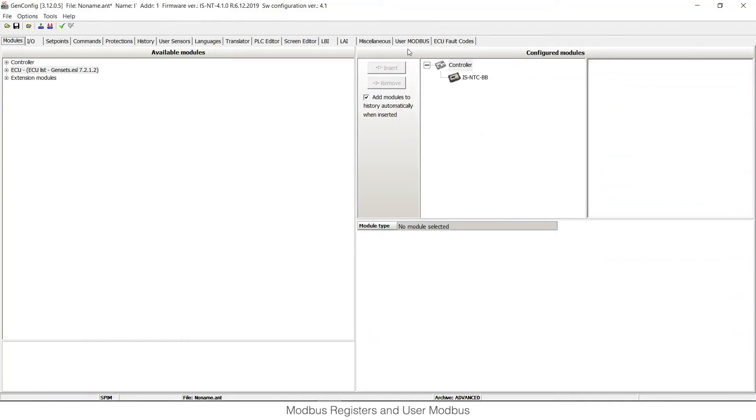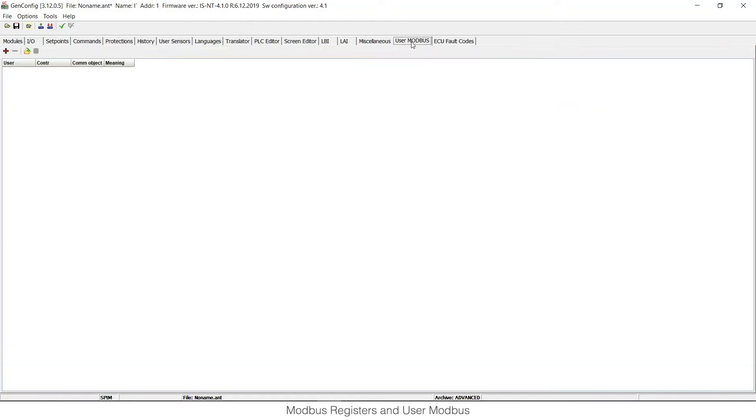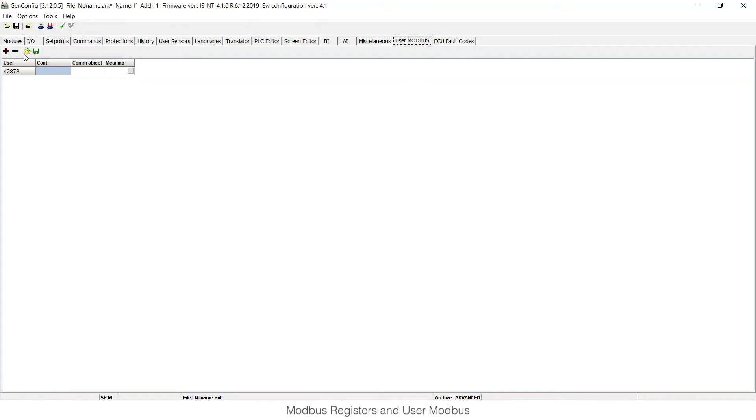If you would like to read these values, these registers, in a different order, you can use functionality of COMAP controllers which is called User Modbus. User Modbus allows you to read up to 127 registers in your selected order.